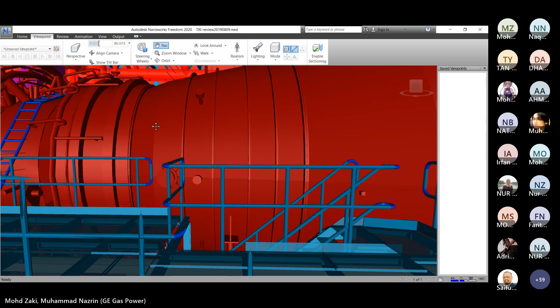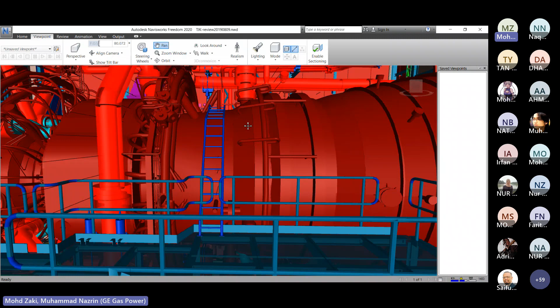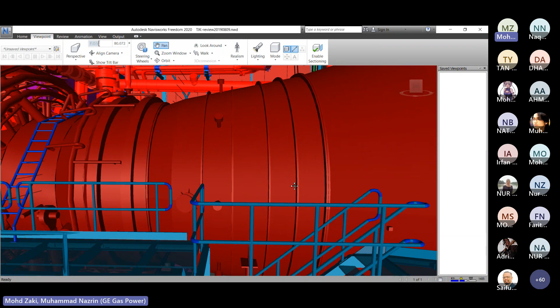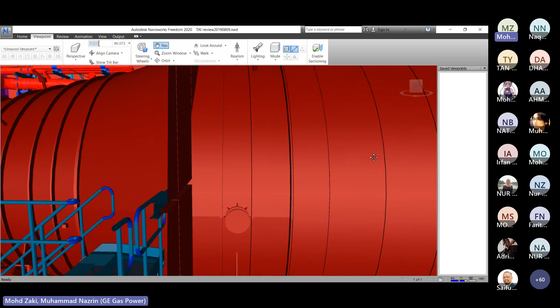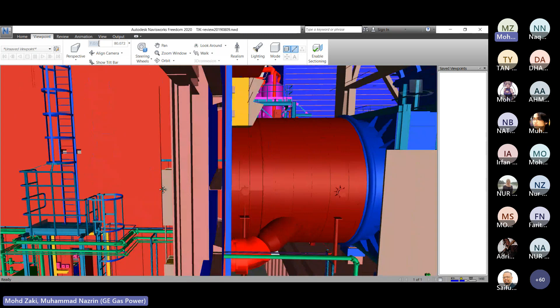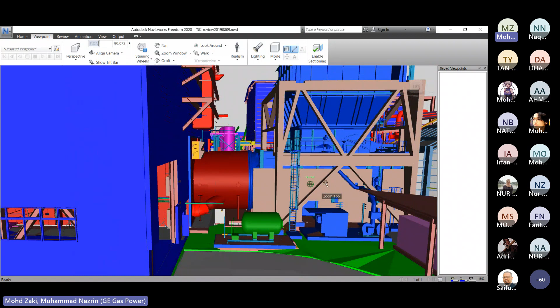So just now I mentioned we have two stages of combustor, the EV and also the SEV combustor, for fuel gas. So this is the EV, we have 24 combustors here, and also ACV, we have 24 combustors here. So we have a double combustor here. This is the combustion chamber, and before this is the compressor. We have the compressor here, this is the combustion chamber, and here we have the turbine. The hot gases will run through this compartment, going through here, and will be sent out to the HRSG.